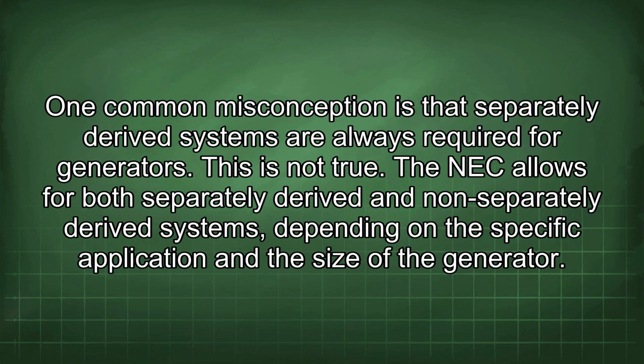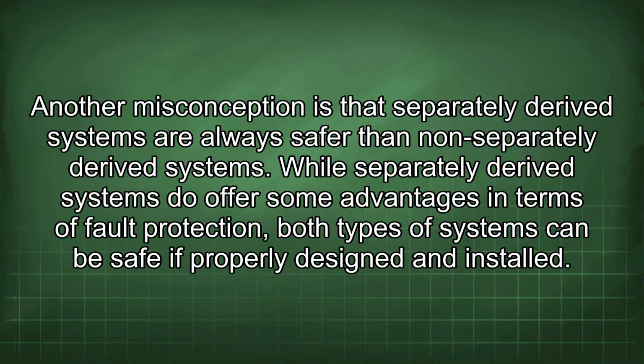One common misconception is that separately derived systems are always required for generators. This is not true. The NEC allows for both separately derived and non-separately derived systems, depending on the specific application and the size of the generator. Another misconception is that separately derived systems are always safer than non-separately derived systems. While separately derived systems do offer some advantages in terms of fault protection, both types of systems can be safe if properly designed and installed.